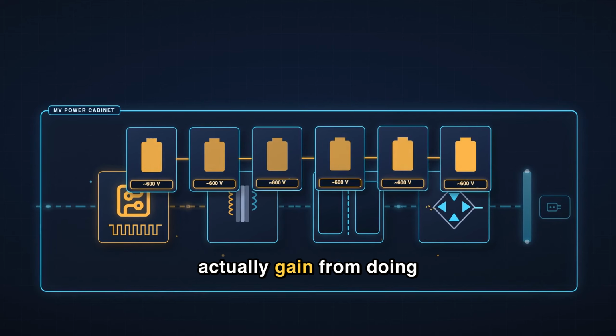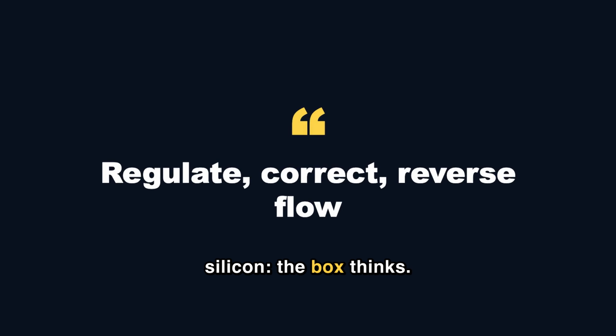So what do you actually gain from doing it all in silicon? Here's the real payoff: the box thinks. The old iron transformer was a dumb pipe; this one is a controller. Because software commands those fast switches thousands of times a second, the box can actively hold the output voltage steady even as demand jumps. It can clean up the power factor, squaring up messy current so the grid isn't dragged out of shape by the load.